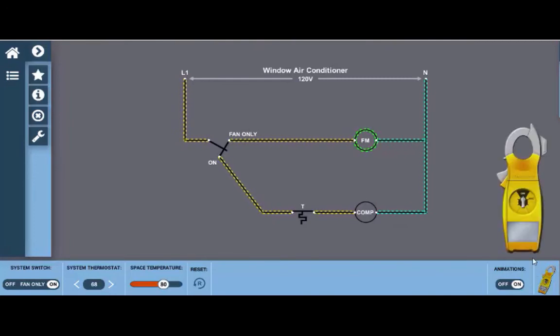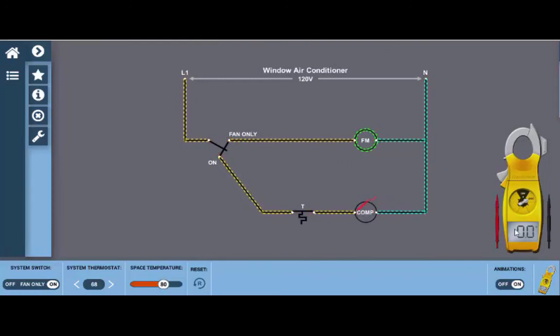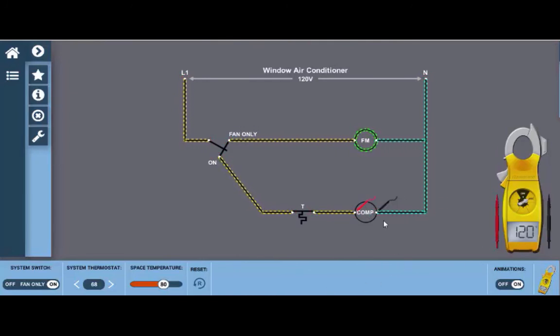If we click on the meter again and click to AC volts and we drop the leads across the glowing hot spots at the compressor we can see that we have in fact 120 volts going to the compressor and it's not operating, so this indicates we have a compressor malfunction.